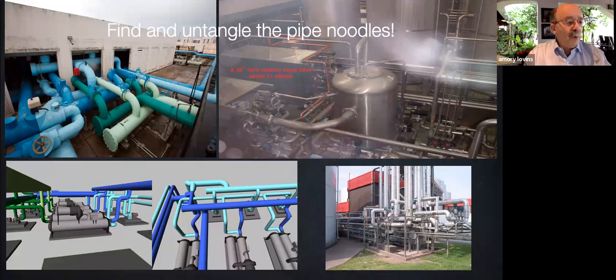Now look again at that image on the one to the right of it, with the aqua and blue pipes. If the big sort of purple pipe running across the ends of the chillers were rotated a bit around its axis, all but the lowest of the elbows between it and the chillers would vanish. Probably the dark green pipes of the lower left could be straightened out too. I think the record holder for untangling pipe noodles may be a brilliant Stone and Webster engineer I met who fixed the layout of the front end of an ethylene plant to cut the number of elbows from 29 to 3. These were stainless steel elbows, almost a half meter in diameter, therefore extremely expensive.